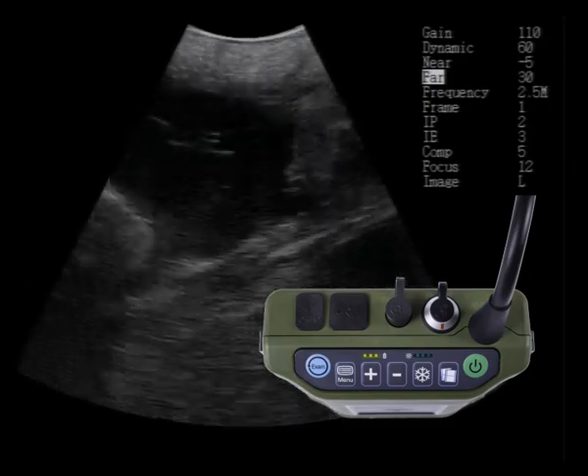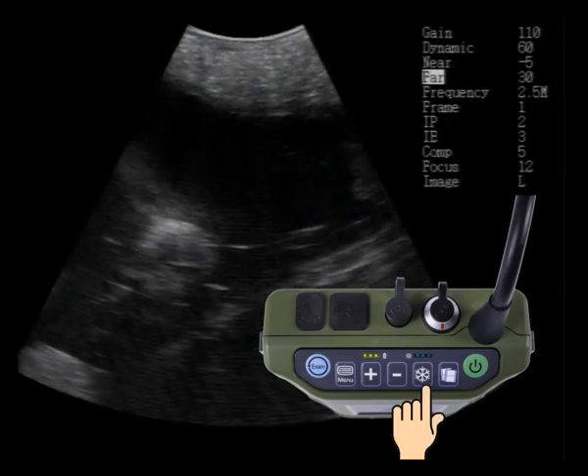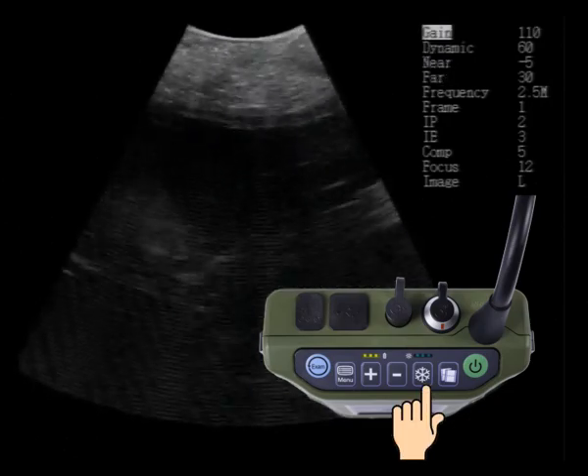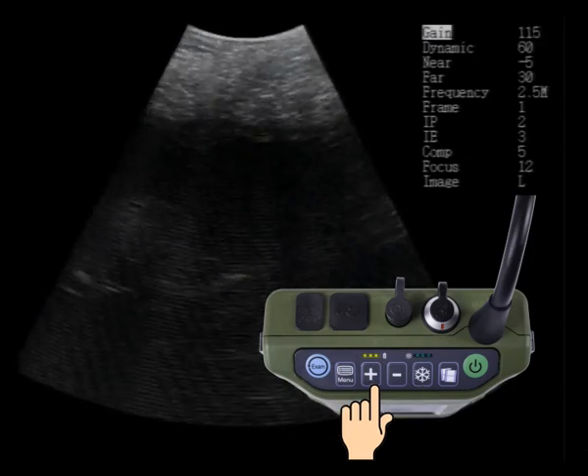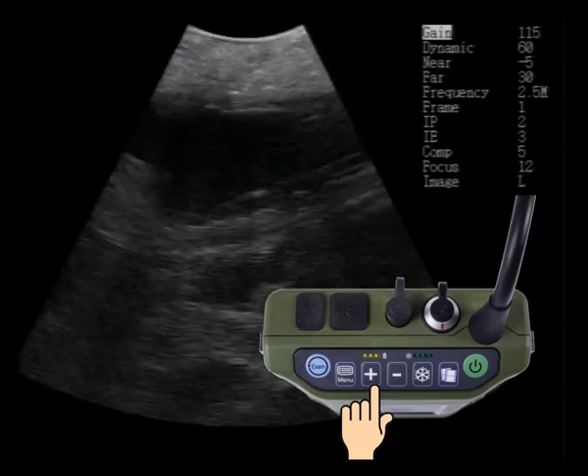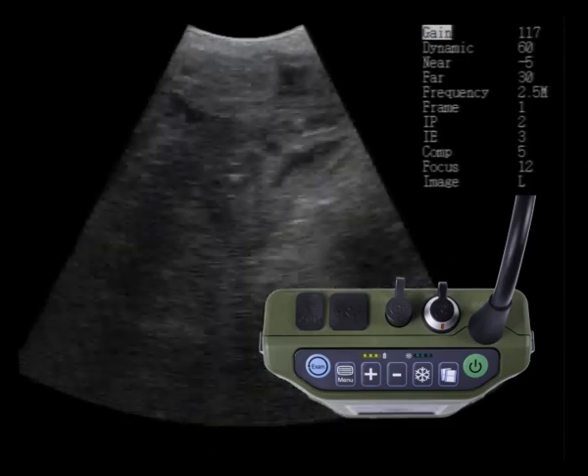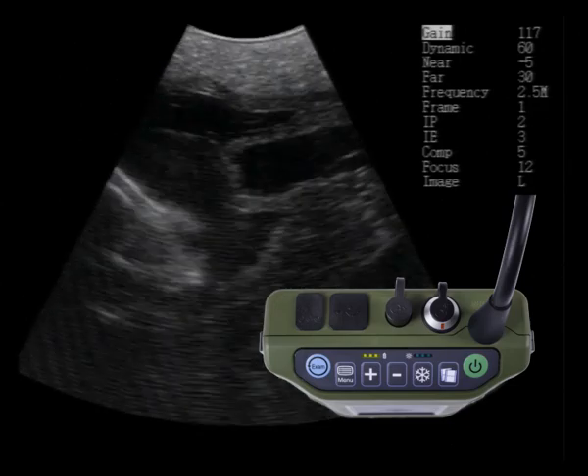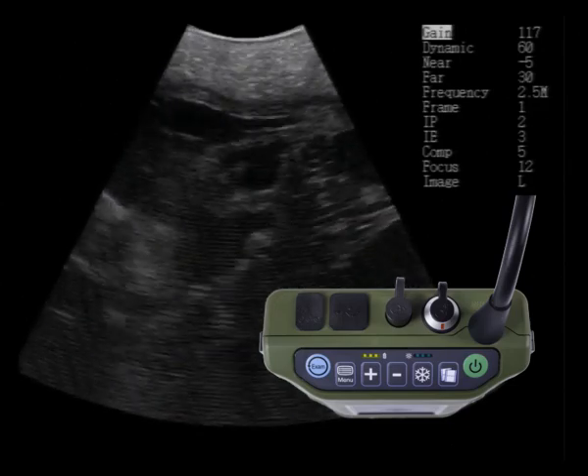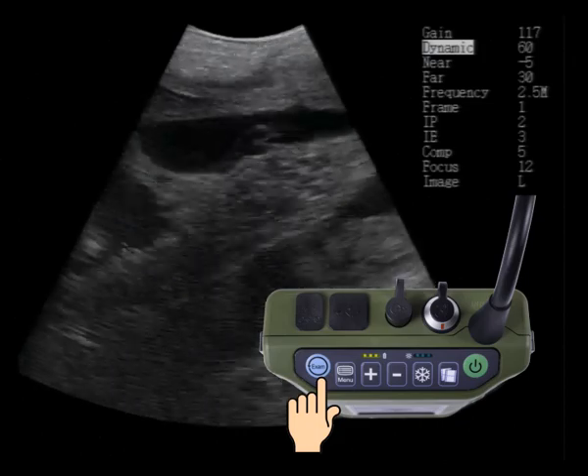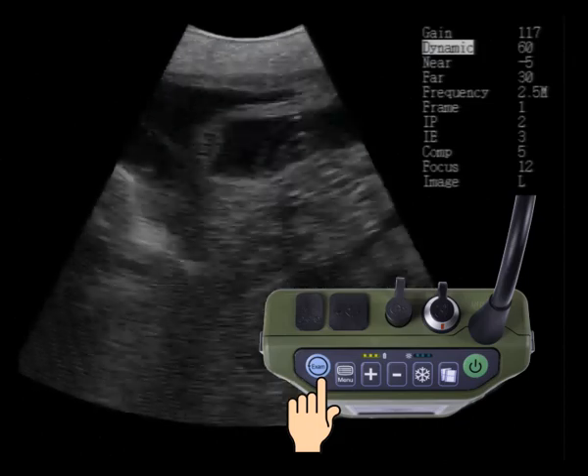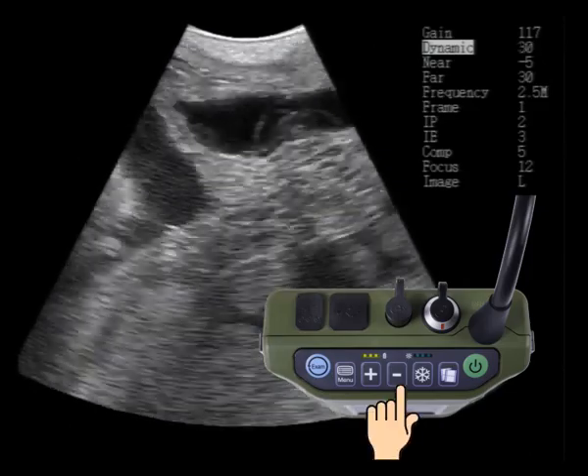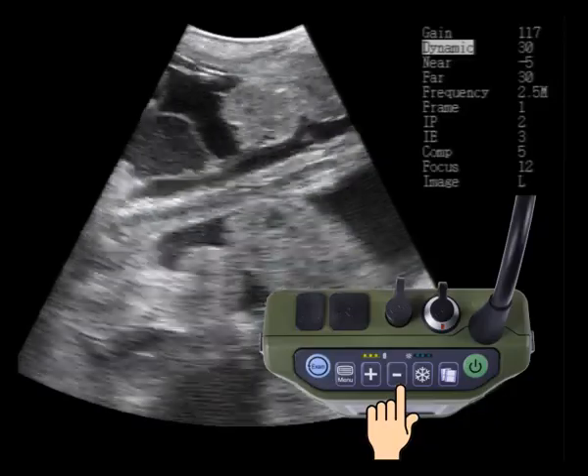We're going to scroll back up some more and increase the overall gain from 110 up to 117. Still not completely happy with this image, so let's scroll down to dynamic and lower the dynamic range right down to 30. Note how bright that image is getting behind us.